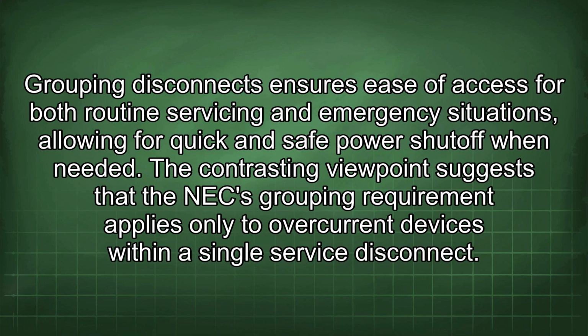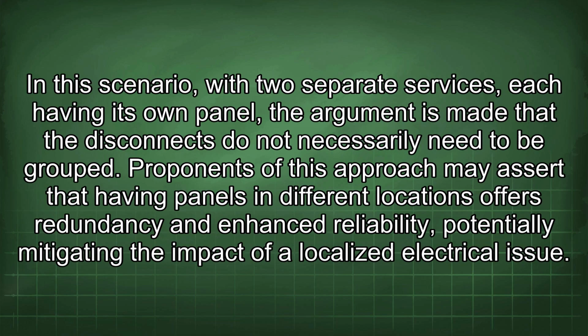The contrasting viewpoint suggests that the NEC grouping requirement applies only to overcurrent devices within a single service disconnect. In this scenario, with two separate services, each having its own panel, the argument is made that the disconnects do not necessarily need to be grouped. Proponents of this approach may assert that having panels in different locations offers redundancy and enhanced reliability, potentially mitigating the impact of a localized electrical issue.